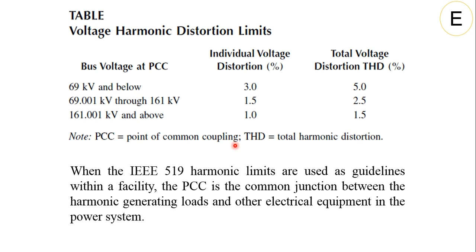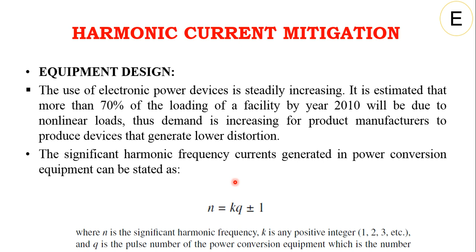Those who know harmonics have a very common equation, kq plus or minus 1, where k is any positive integer and q is the pulse number of the power conversion equipment. Suppose we have a 12 pulse converter and our positive integer is 1, so n equals 1 into 12 plus or minus 1, so 13 and 11. So from this 12 pulse converter, the 11th and 13th harmonics are most severe, and these are the significant frequency generators. This is the simulation of the 12 pulse converter and its output voltage.